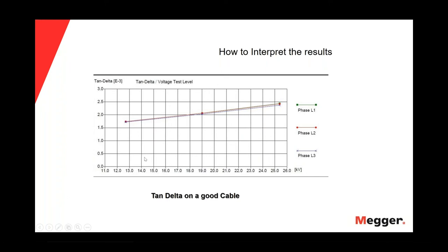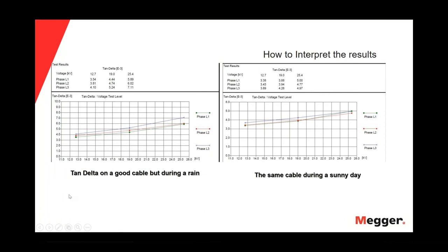Well, we will see some graphics of tan delta. The first one is the tan delta on a good cable. If you see, the three phases have pretty much the same graphic, the same behavior. In the next slide, we have the same cable, but we can see in the graphic on the left that the tan delta test was made during rain. So the values of the tan delta are higher in this test. But for the same cable, we did the tan delta on a sunny day, and we get a better result, or lower values for the tan delta, which means that the weather conditions can also affect the results of the tan delta test.